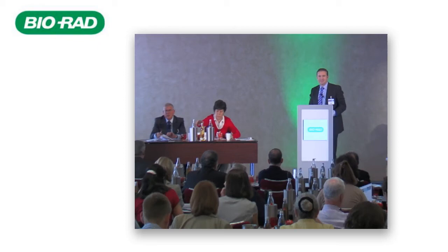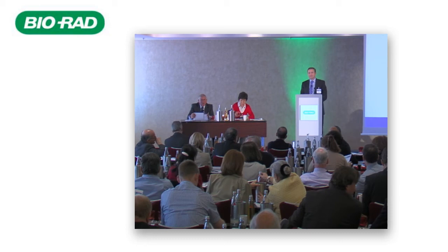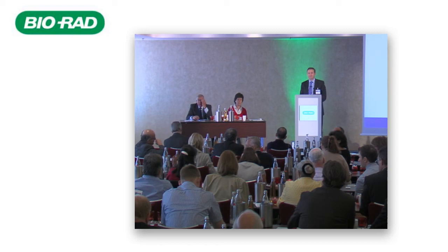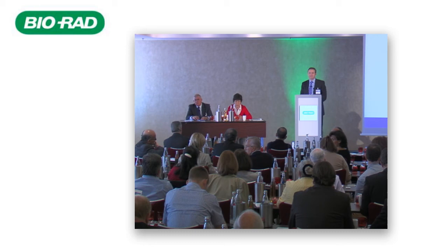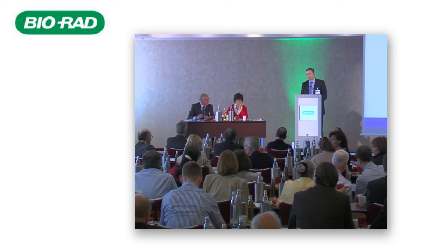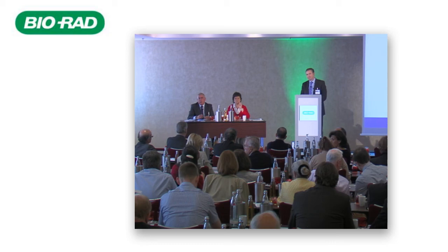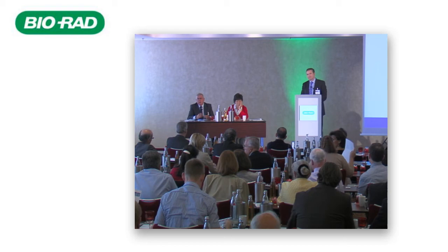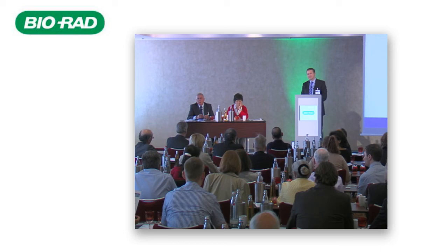Just a few minutes ago when we were voting on who defines the quality goal for the labs, one of the labs said, yes, we do that. But is it a true statement that we define analytical goals? I think it's not true, because simply what we do is allocate the current performance to one of, for example, the biological variation levels, because once the assay has been designed by the manufacturer and released to the market, there is no power on this earth to make us change the CV to less than what's been stated by the manufacturer or change the bias.